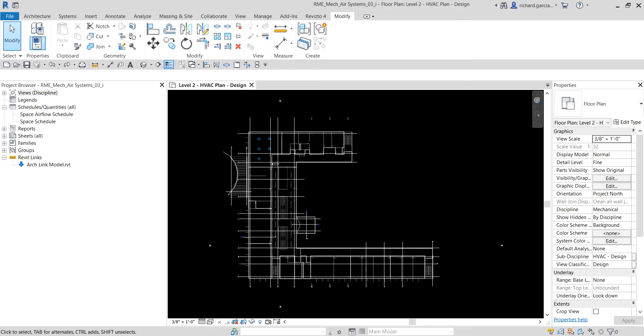A Revit MEP system is the logical connection between system components such as air terminals and mechanical equipment. This logical connection allows Revit MEP to perform various analyses including energy analysis. You create air systems by placing air terminals and mechanical equipment, then create the logical connection between the system components. After creating the logical connection, you then create ductwork to physically connect the system components.